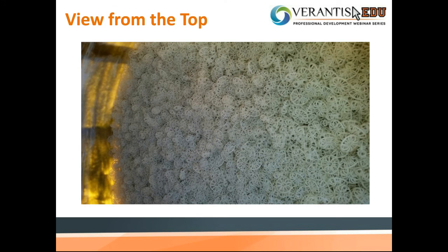As I mentioned before, we do have some customers who choose to go quite a few years before changing the packing. This picture shows an example of a customer who came to us who hadn't replaced their packing in 10 years. Originally their scrubber was designed to operate at about a pressure drop of 1.5 inches across the scrubber. Over time, this pressure drop continued to increase until they called us and said they had a pressure drop measuring about 6.5 inches. After checking the nozzles and the mist eliminator, I asked them to take a picture of the packing and send it over. And the picture they sent looked like the packing was still pretty new.